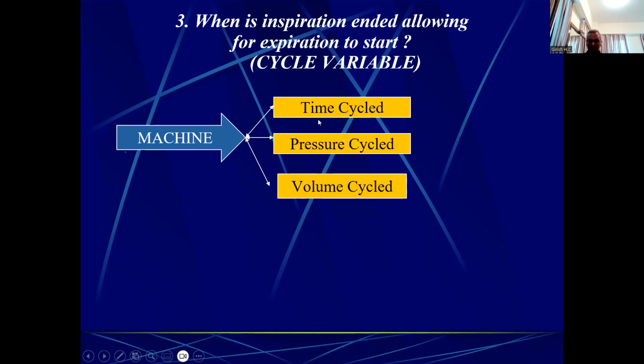So it is time cycle. The only way the machine knows how to cycle is by the time you set. Is it clear? Yes. Pressure cycling and volume cycling we don't do anymore. And don't get confused with pressure limiting and volume limiting. That we still do, but that is the limit. We set the limit for this much pressure, but that pressure may be held for 1 second or 1.5 seconds. Cycling, we are talking about, is mainly by time cycle.